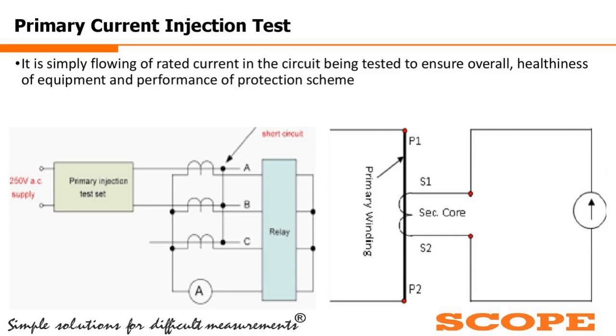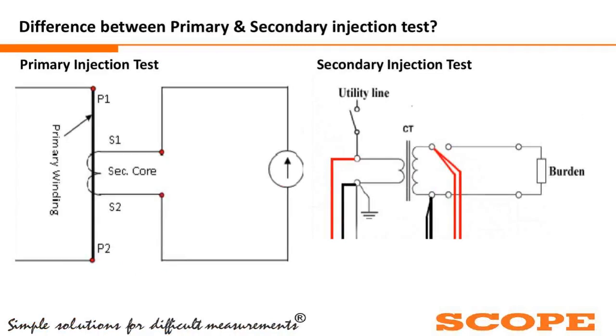The difference between primary and secondary current injection: in the primary current injection test, we directly inject a rated current from the primary side of the current transformer and accordingly check how much current is flowing from the secondary side. CTs are designed for one ampere or five ampere secondary current, so after injection of the primary rated current we check whether the secondary current is one ampere or five ampere only. This is the direct method to check the behavior of the primary and secondary current.